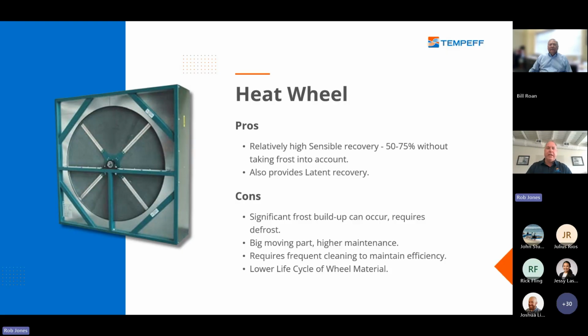Probably the most common out there is the heat wheel, relatively high sensible recovery of 50 to 75%. It also can provide latent recovery. So energy wheels do come with a desiccant coating. The cons, it has a significant frost buildup problem, and this is very particular to energy wheels where a preheat or defrost strategy is required to protect that desiccant coating that is on the cold side of the exchanger. Big moving part, higher maintenance.